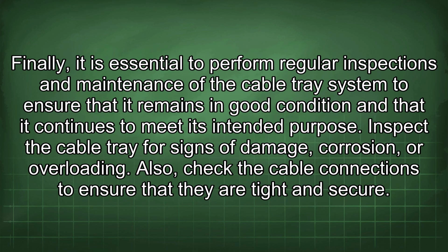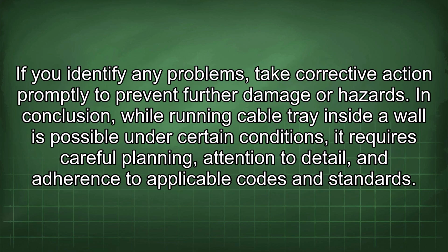Finally, it is essential to perform regular inspections and maintenance of the cable tray system to ensure that it remains in good condition and that it continues to meet its intended purpose. Inspect the cable tray for signs of damage, corrosion, or overloading. Also, check the cable connections to ensure that they are tight and secure. If you identify any problems, take corrective action promptly to prevent further damage or hazards.